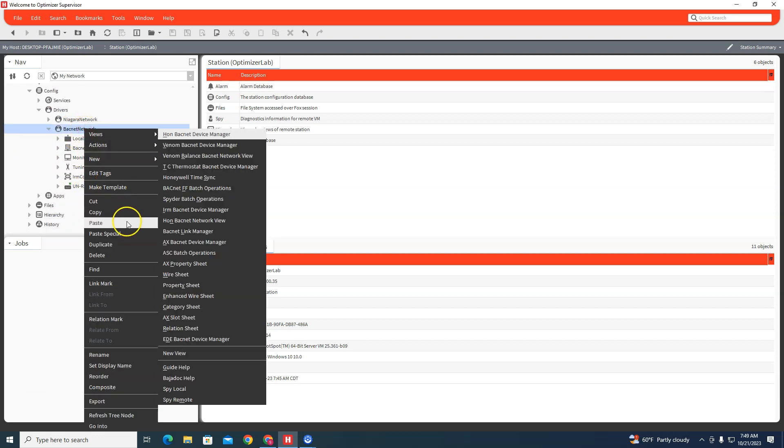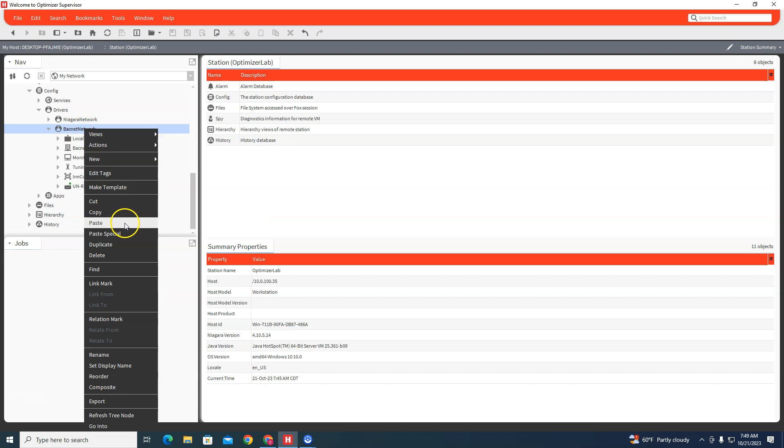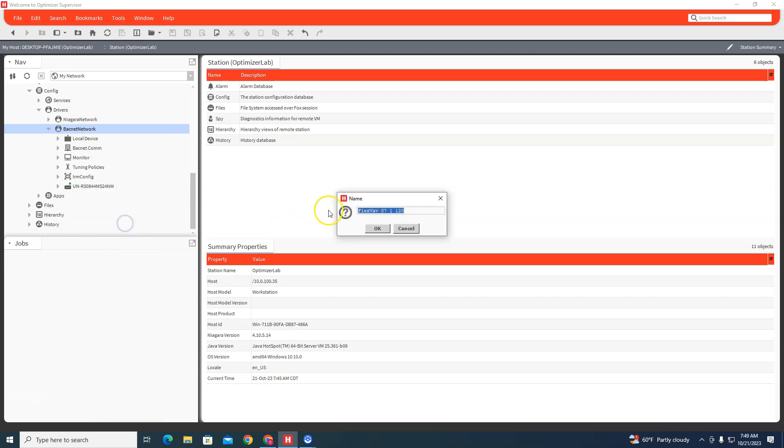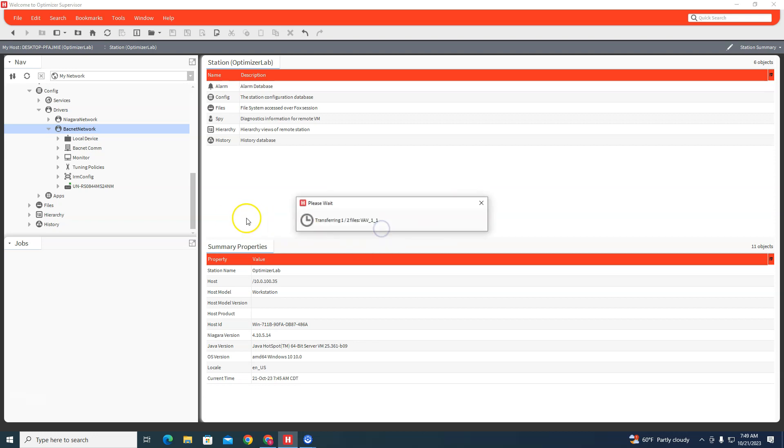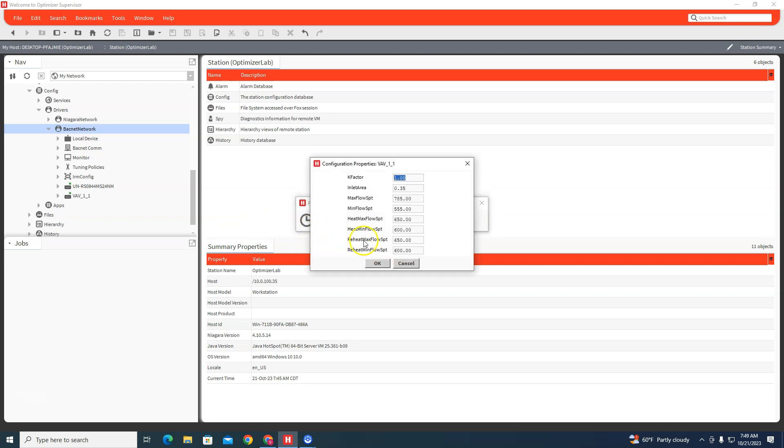We paste that template in, and then you can name the controller VAV_one_one. And now you could set in your K-factor, your box size, your min max flows, everything right here.